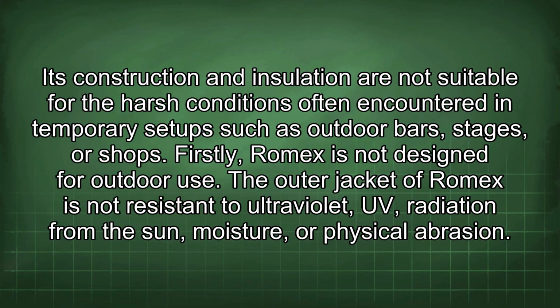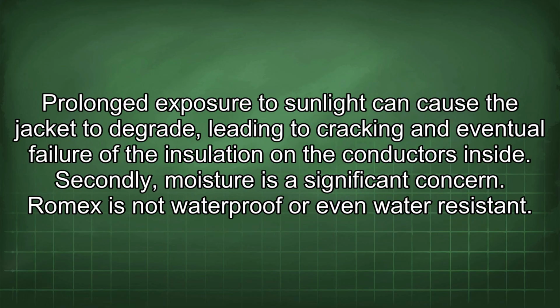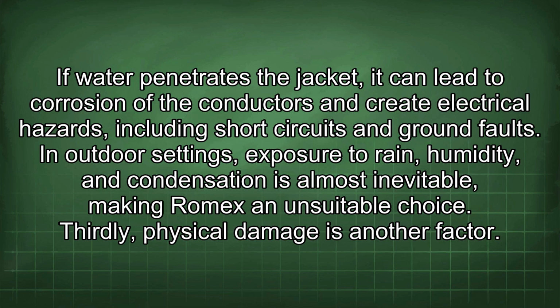Firstly, Romex is not designed for outdoor use. The outer jacket of Romex is not resistant to ultraviolet (UV) radiation from the sun, moisture, or physical abrasion. Prolonged exposure to sunlight can cause the jacket to degrade, leading to cracking and eventual failure of the insulation on the conductors inside. Secondly, moisture is a significant concern. Romex is not waterproof or even water resistant. If water penetrates the jacket, it can lead to corrosion of the conductors and create electrical hazards, including short circuits and ground faults. In outdoor settings, exposure to rain, humidity, and condensation is almost inevitable, making Romex an unsuitable choice.